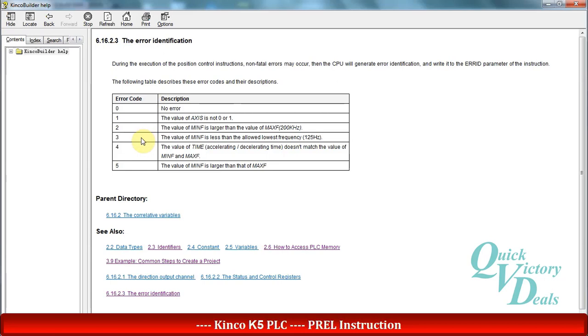The error number 3 means that the min-f is not correct and it should be upper than 125 hertz. The number 4 means that our acceleration or deceleration time is not correct choice for our min-f or max-f.